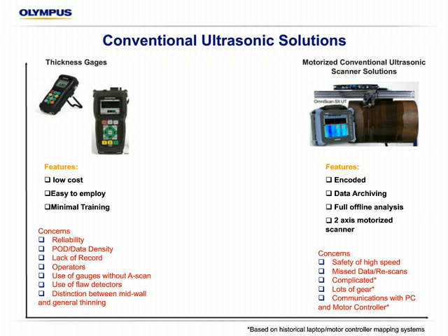So if we're going to do a tank or a vessel of some kind, you get the entire area that you program to scan versus more sampling random points that you would get with a thickness gauge. But there are some concerns with that methodology.